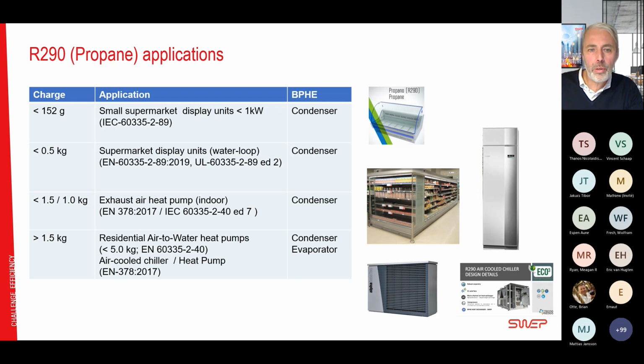In supermarket display units, there is a possibility to use a charge up to 500 grams, 0.5 kilos. And this is governed by the standard 60335-2-89, and we also have a UL standard here up for EPA approval. And typically, they are being used in this type of system, display unit, and on the top there is one or several condensing units, typically using a BPHE as condenser.